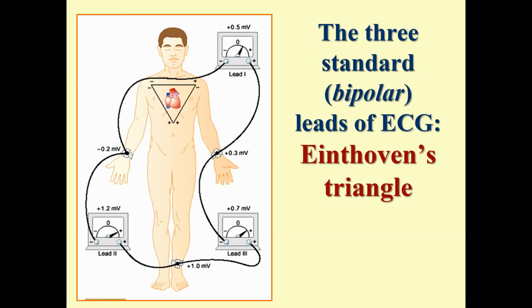And actually, the electrocardiograph device is simply like a voltmeter, a very complicated one. It measures the difference of potential that constantly changes. And therefore, for measurement of difference, we always need a pair of electrodes. We cannot register a difference using one electrode. It's always a pair. But these pairs can be different.